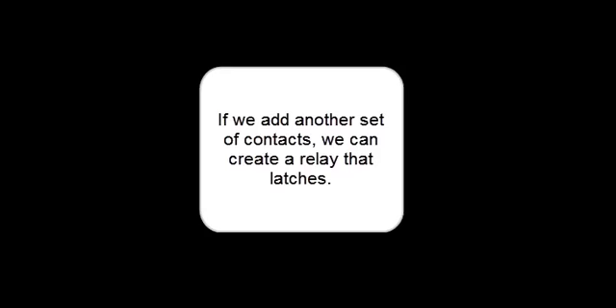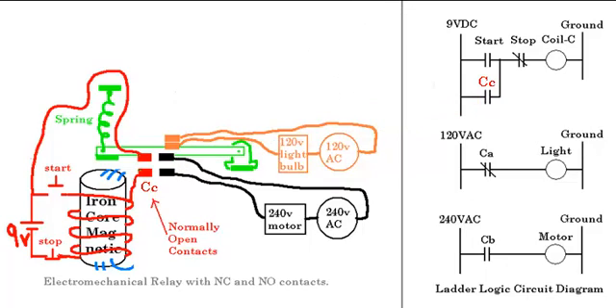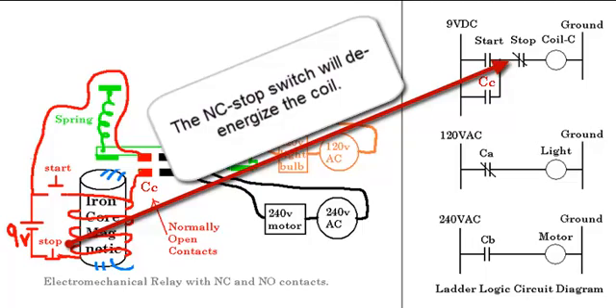If we add another set of contacts, we can create a relay that latches. The additional contacts will keep the coil energized even after the start switch is released. The normally closed stop switch will de-energize the coil.